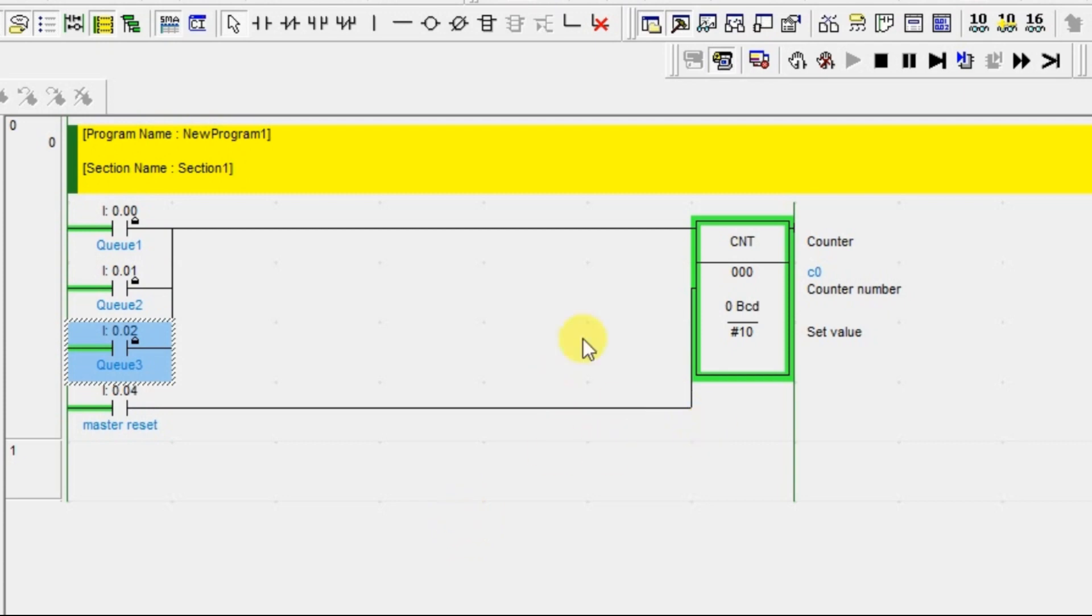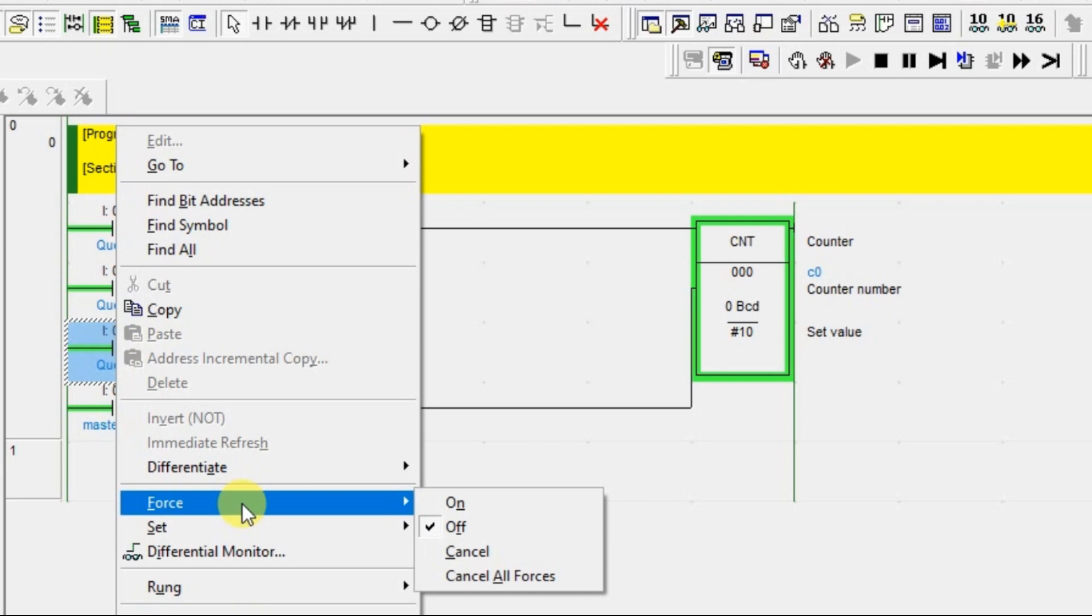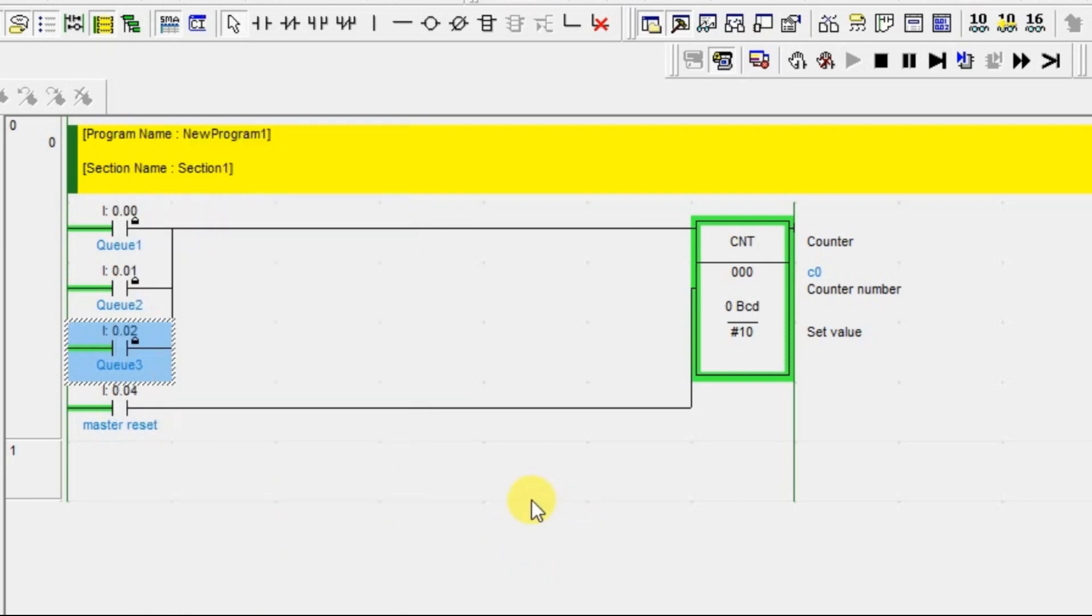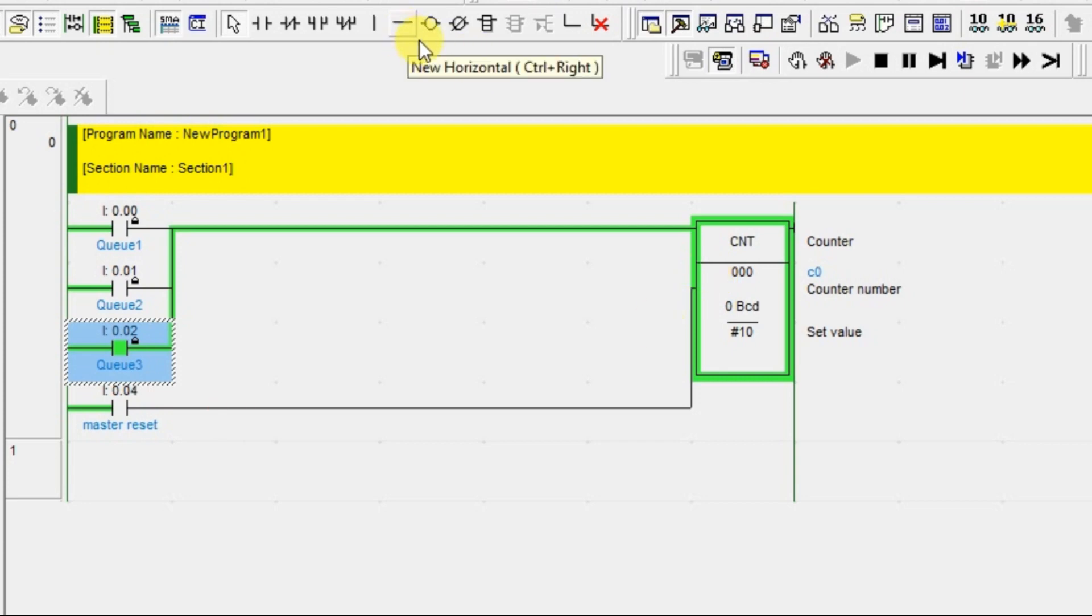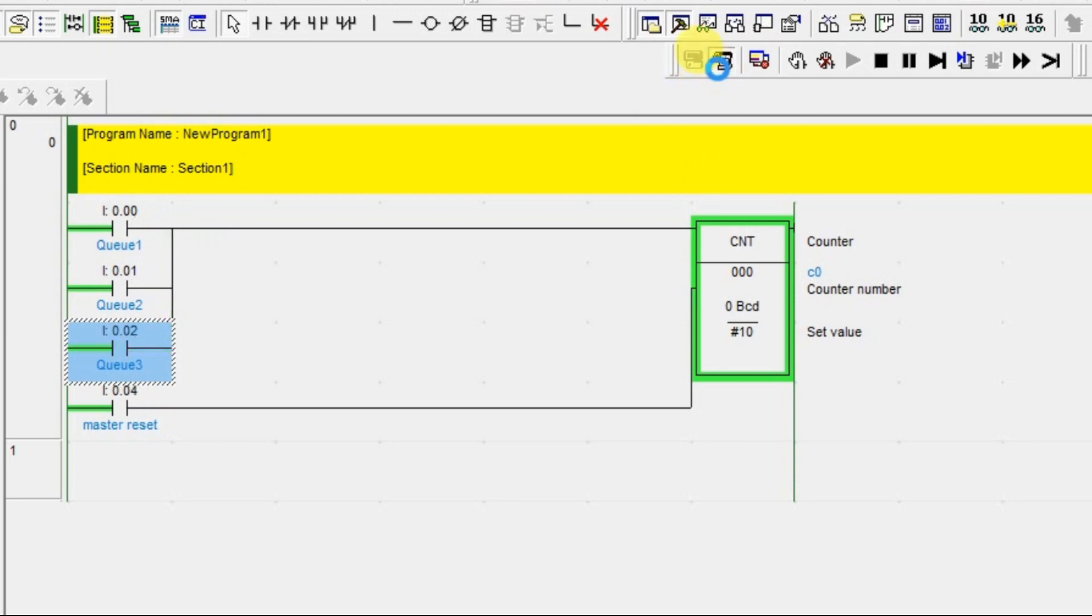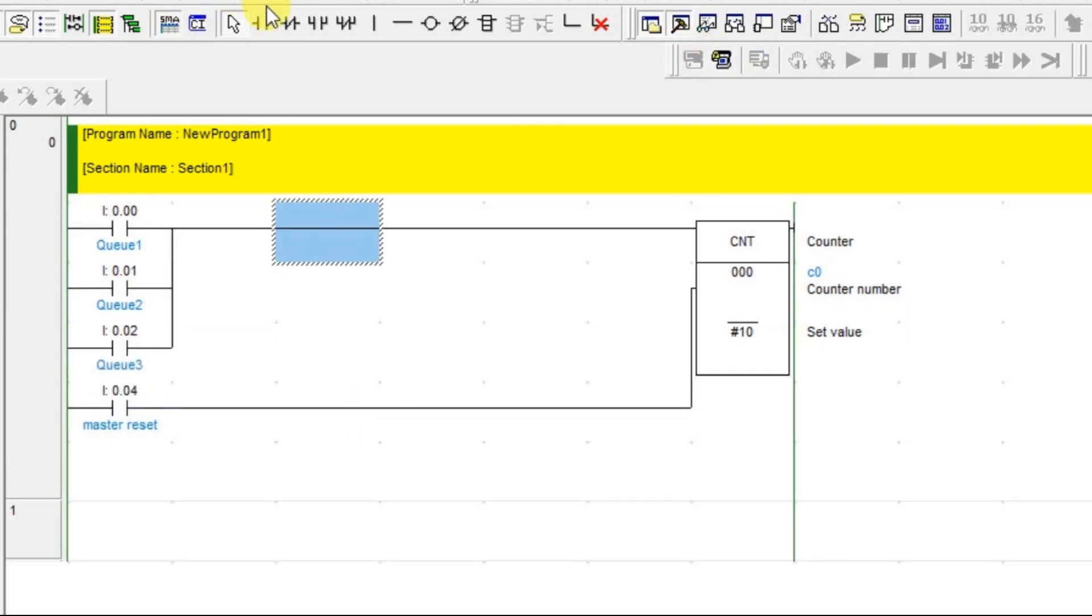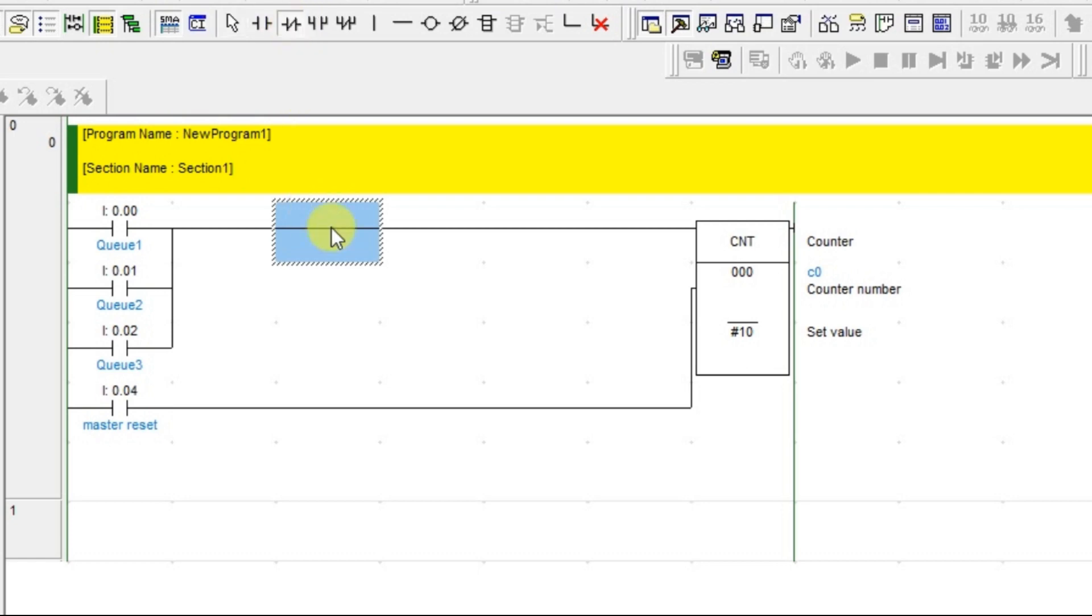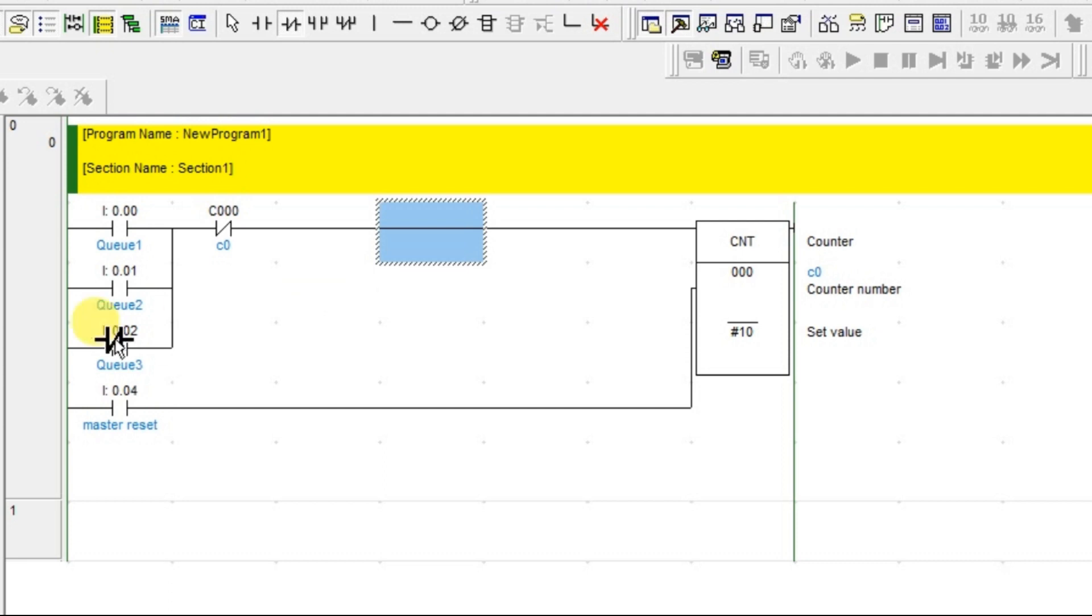The counter is on. Now if someone is trying to enter, what will happen? See, the entry is allowing to the counter. The counter has reached but still the entry is going to the counter. So what we have to do is restrict the entry to the counter. For that, you can add a bit here to restrict the counter. I'm adding the same counter bit as a normally closed contact here.